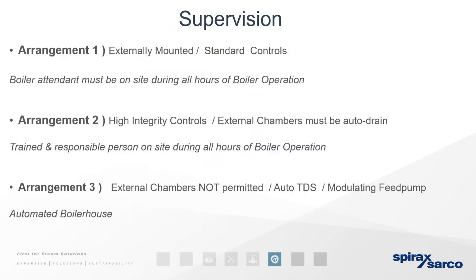So arrangement 1 on supervision. So this is to do with, in the UK, effectively there are various control motor types. So we have safety features and testing criteria, meaning that a boiler house can be designed in these arrangement types, which in turn advises the level of testing and supervision that is required. So arrangement 1, externally mounted standard controls. Boiler attendant must be on site all hours of the boiler operation. So when that boiler is on, there should be somebody present.